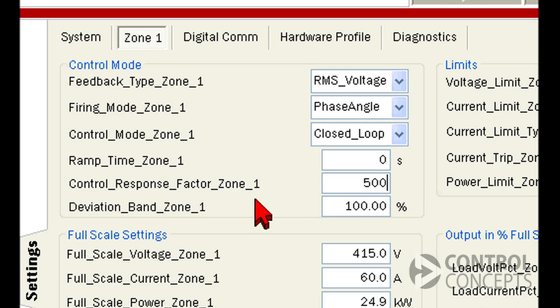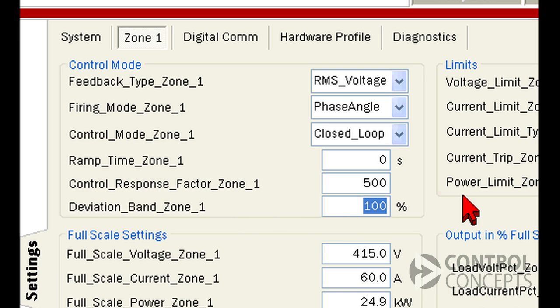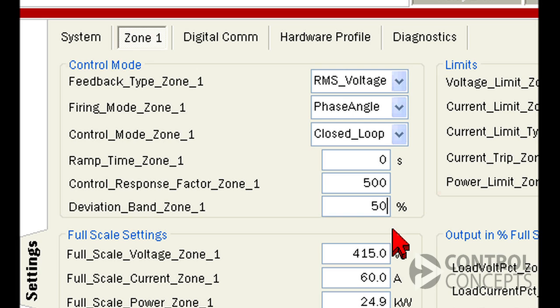The deviation band setting generates an alarm if the controller feedback is a certain percentage over or under the desired set point. This setting is not available on all firmware. Contact Control Concepts if you have questions about your firmware release.